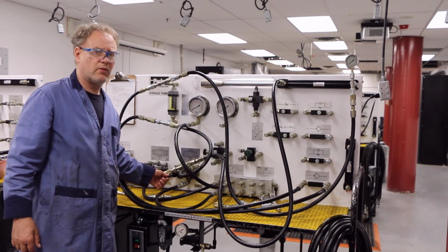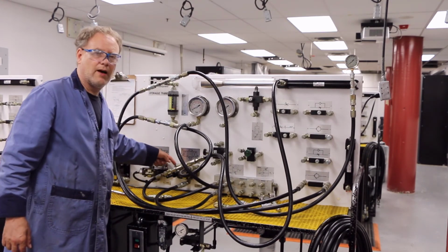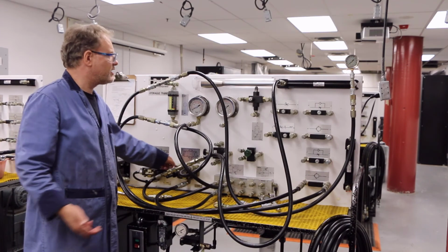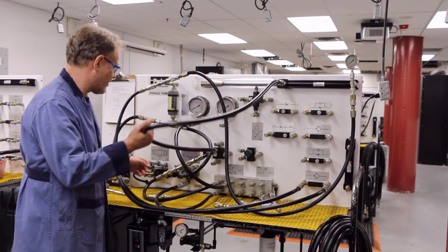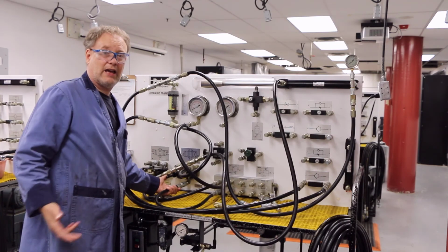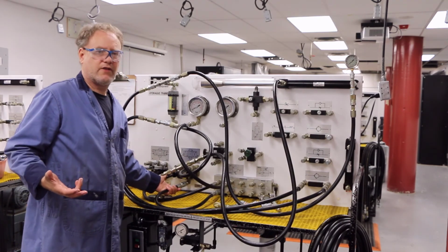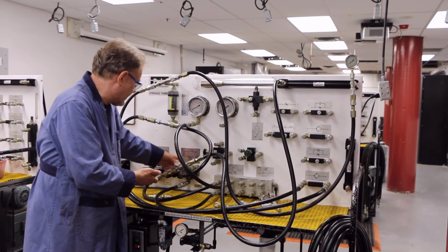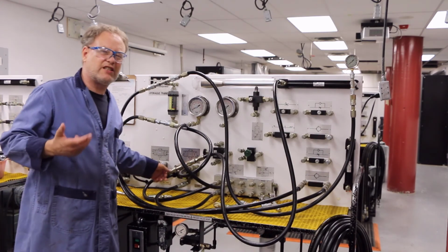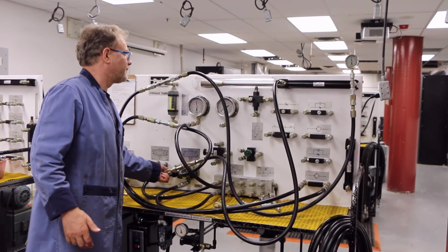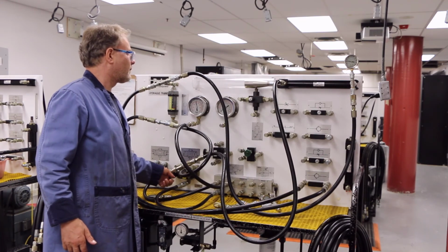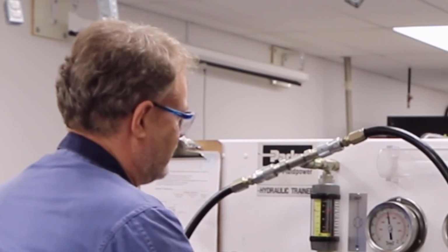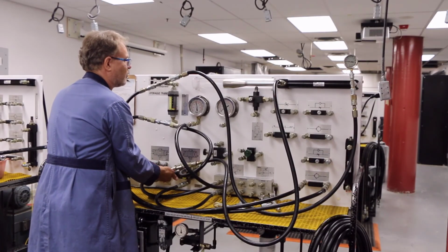Some of you may be thinking, wait a second. This is not hooked up. This is for retraction. Well, it actually will retract, and the reason it will retract is because when I retract it, it will see a little bit of the tank. Actually, it will see a high pressure of the tank. Although the fluid going in here sees the tank because it's actually venting because of the nature of the valve, it will see some pressure and it will retract. Check it out. There you go. So it's actually fully retracted, and we can do this again and watch this. There we go. Nice. And in retraction, it still works in retraction.